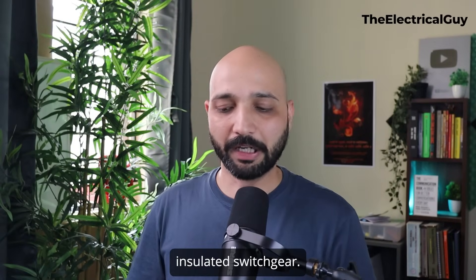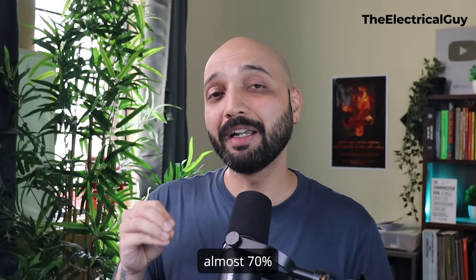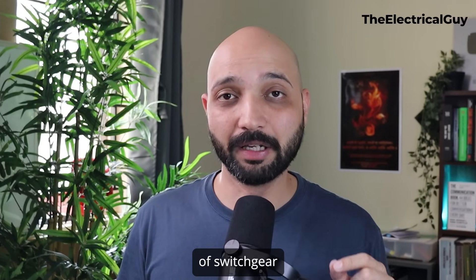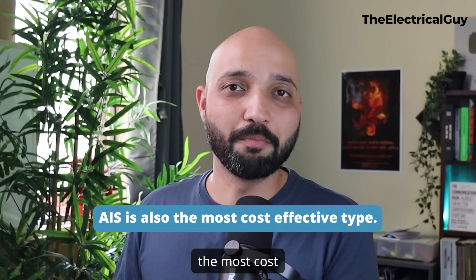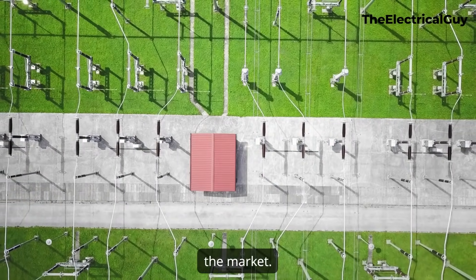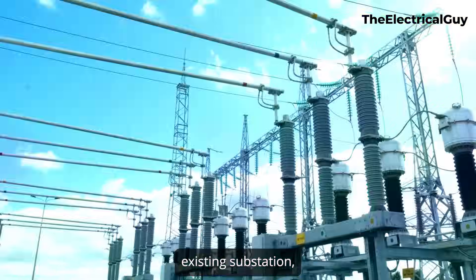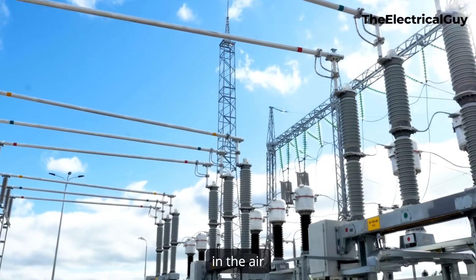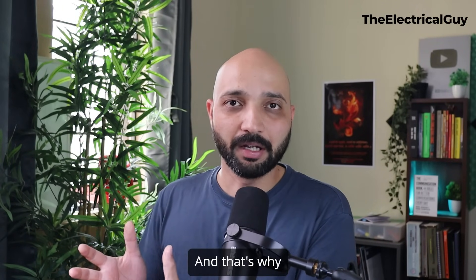Air insulated switchgear — even per the CIGRE report — accounts for almost 70% of substations in the whole world, especially high voltage substations. The reason is it's the most cost-effective solution available. It's also very easy to do future extensions: if your existing substation is full and you want to add another transformer bay, you can do that easily without much trouble with AIS.